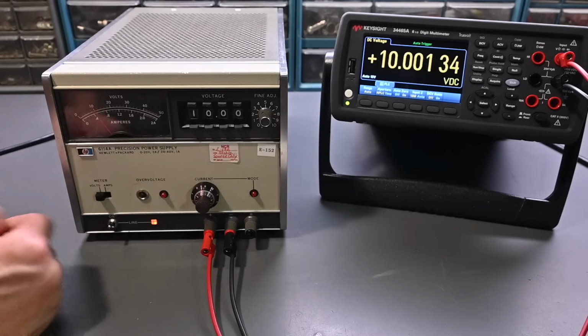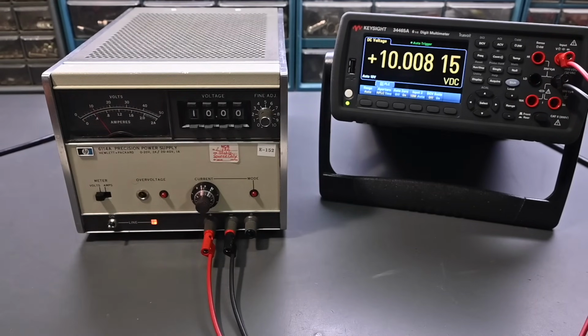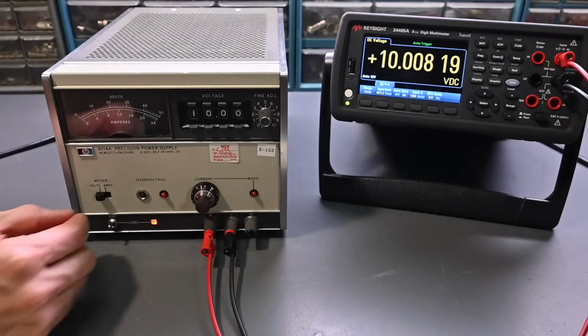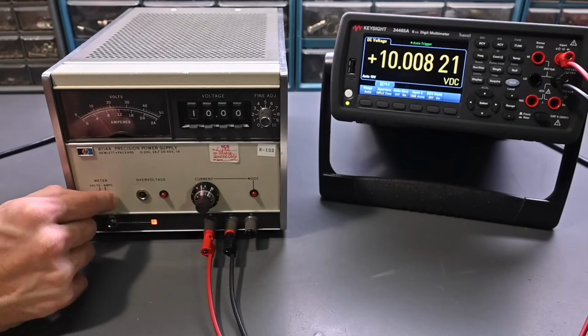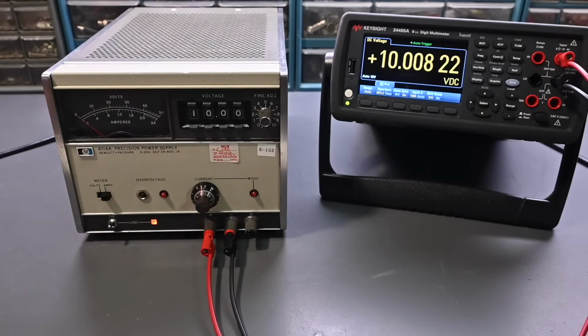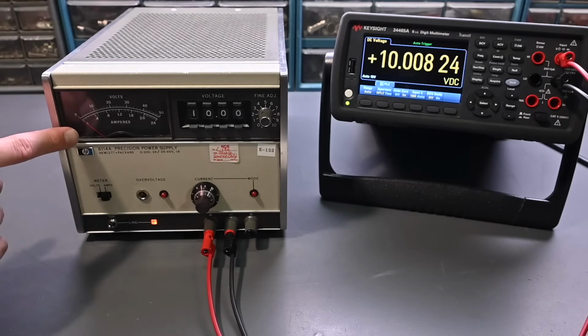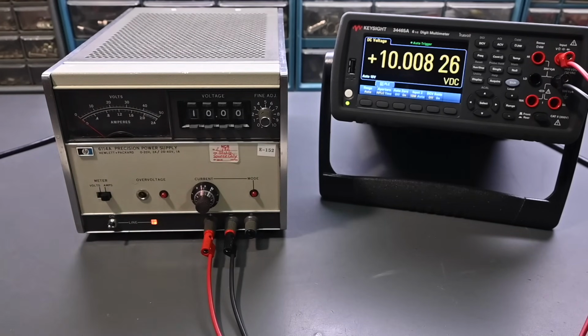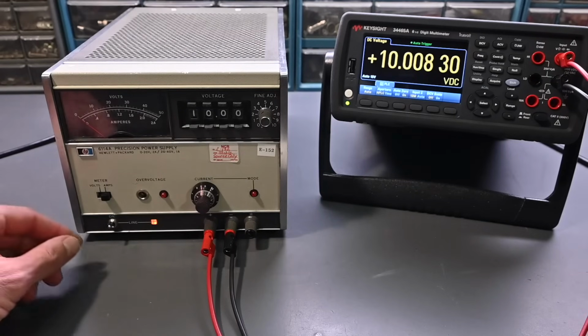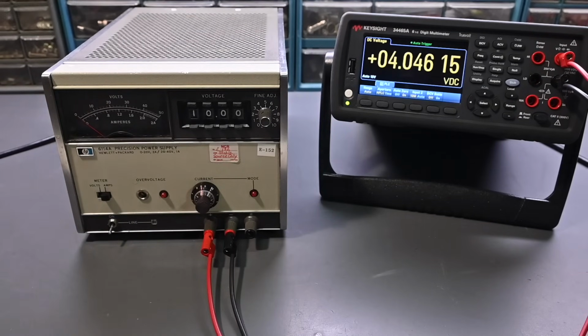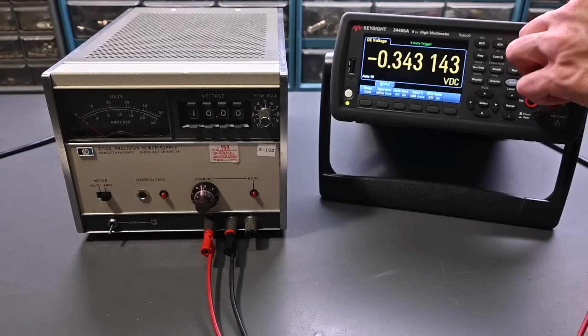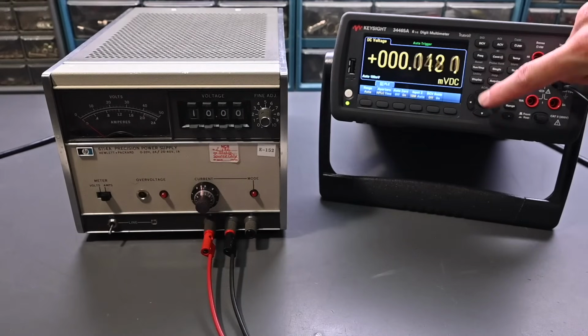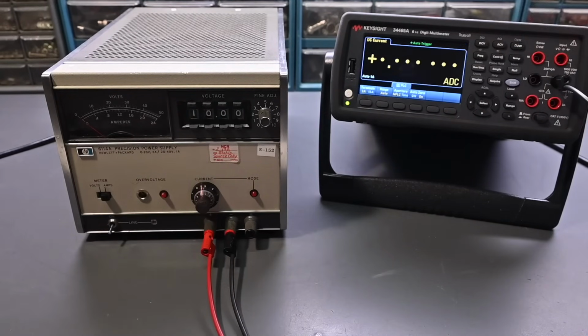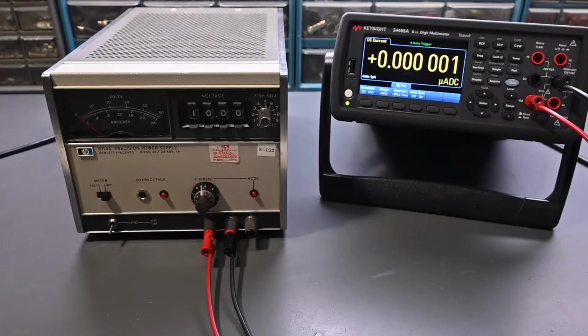Now the other thing is, okay, it's going to work there, so we'll just leave that alone. So it's at 10 volts right now. But this switch right here for volts and amps, if I go like that, that goes over to the amp position. This is sitting at 0. There is no current right now. What I will do is, actually, I'm going to turn that off for a second. Let's just move this over to the current setting right here. DC amps. Okay. And put that on the 10 amp setting.